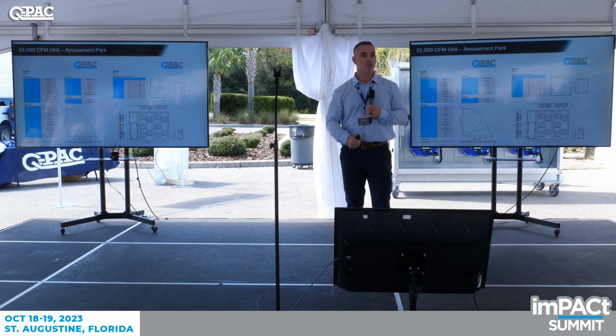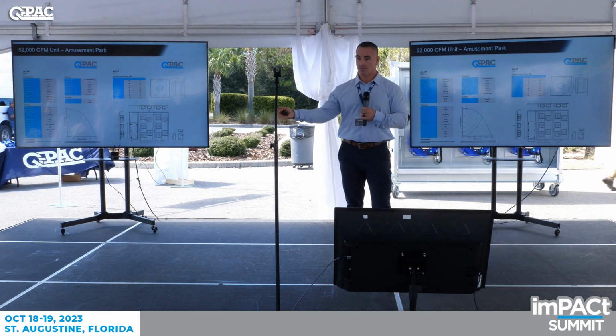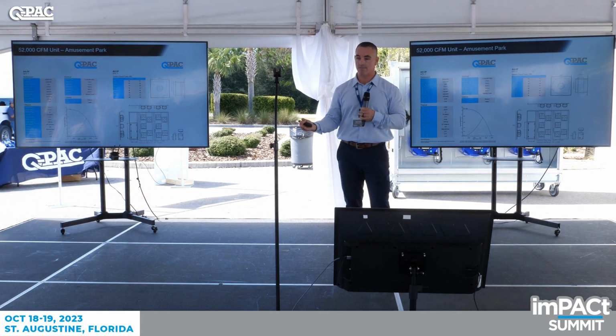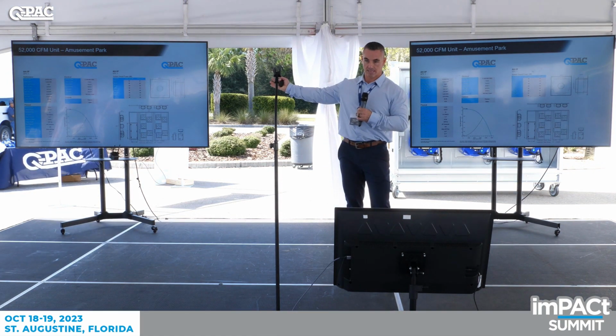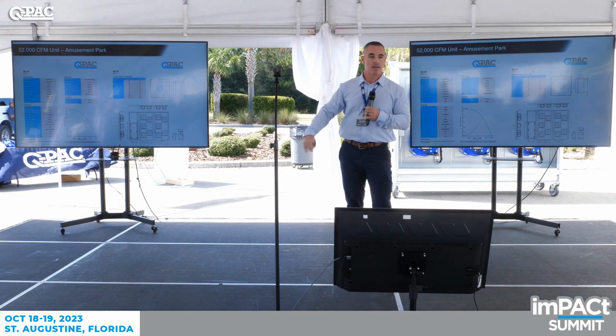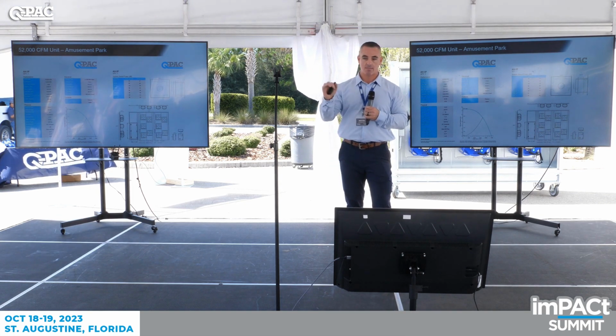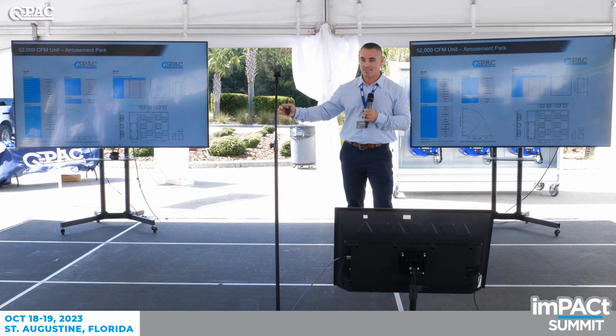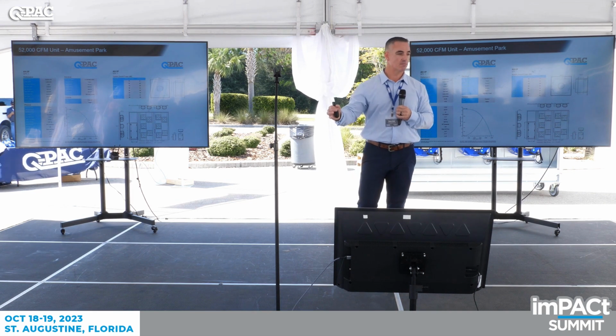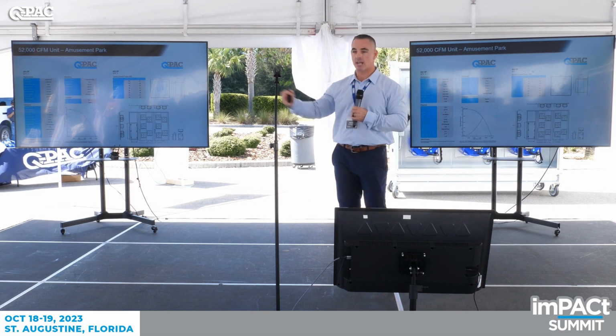So a lot of times, if you don't know what your CFM is, I'll go in and measure the coil face area. I'll do my math, come up with what it should be, max. I'll count the filters, and do another check there.